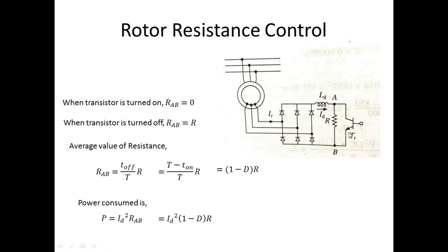It should be noted that this method can only be used in slip ring motors, since we need access to the rotor circuit output. In case of squirrel cage motors it is not possible. So this applies to slip ring motors only.